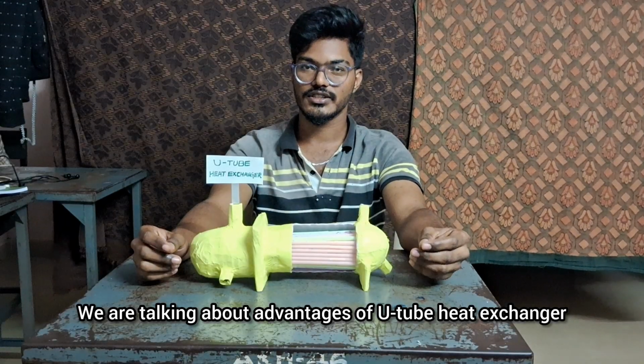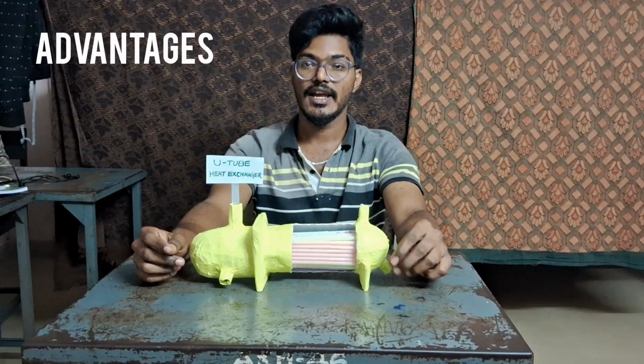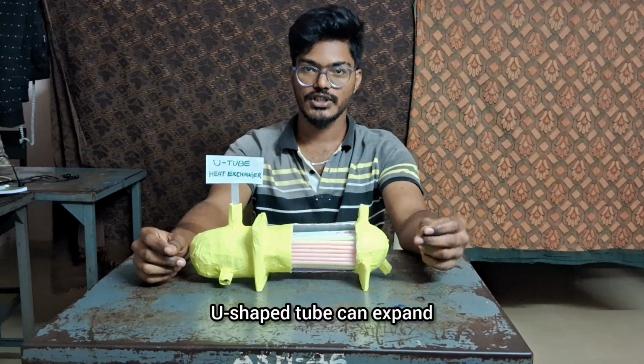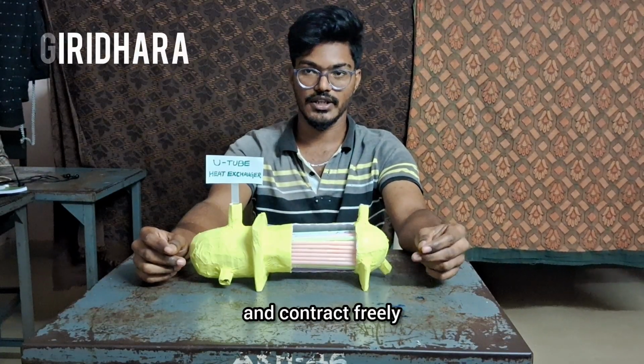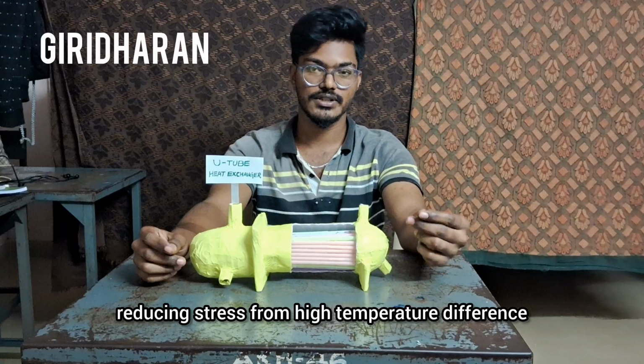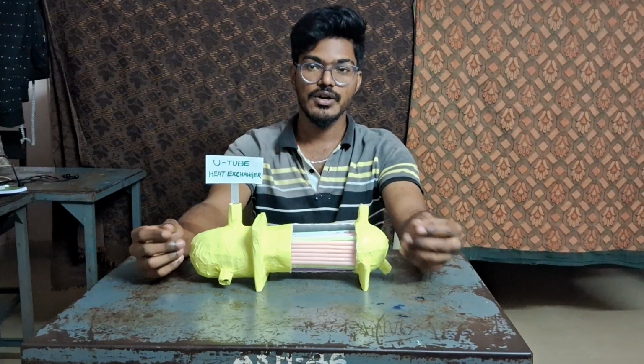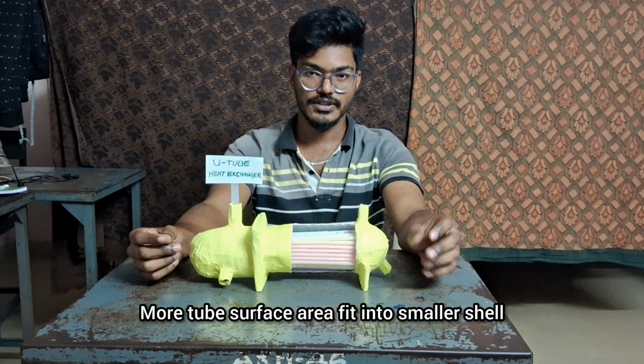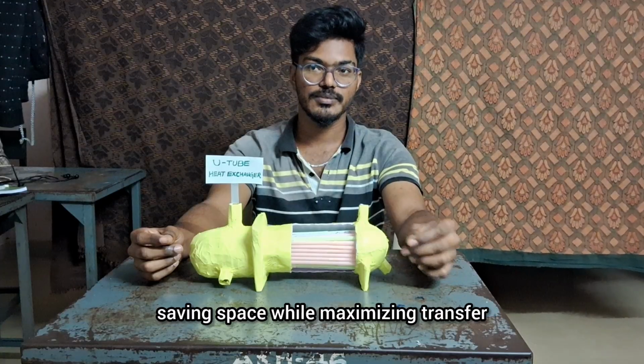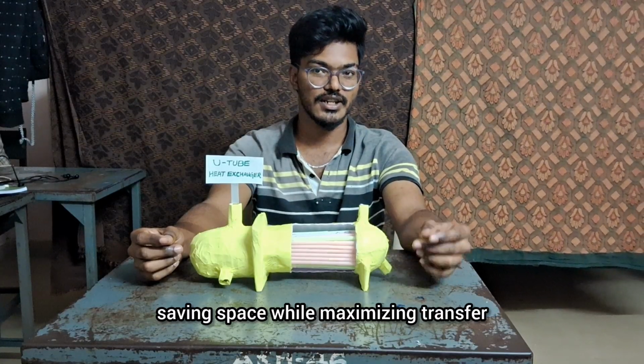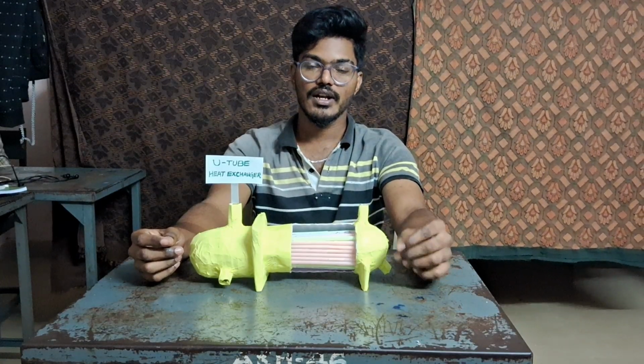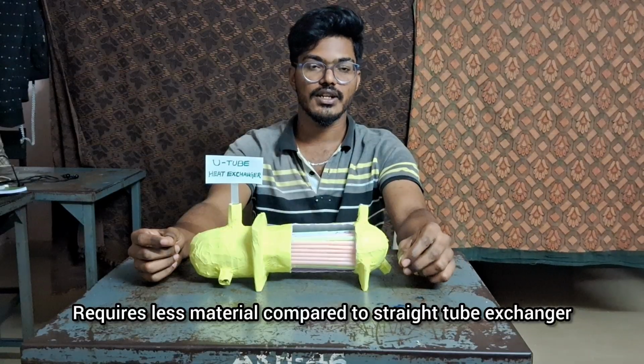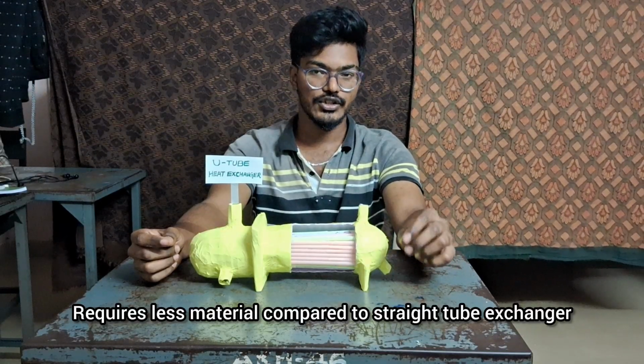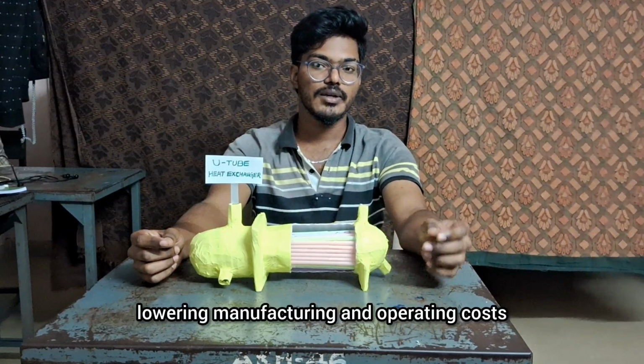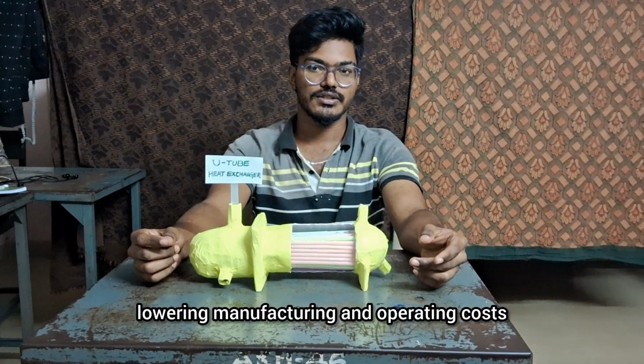Talking about advantages of the U-tube heat exchanger. Handles thermal expansion: the U-shaped tube can expand and contract freely, reducing stress from high temperature difference. Compact design: more tube surface area fits into a smaller shell, saving space while maximizing transfer. Cost effective: requires less material compared to a straight tube exchanger, lowering manufacturing and operating costs.